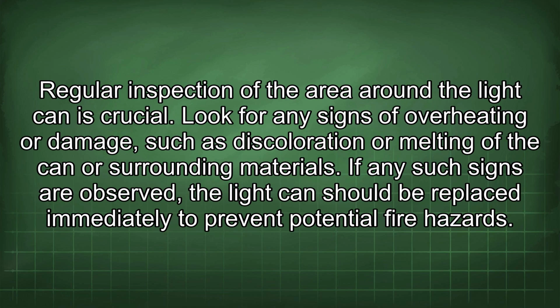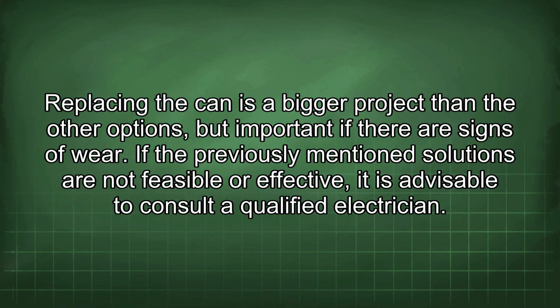Regular inspection of the area around the light can is crucial. Look for any signs of overheating or damage, such as discoloration or melting of the can or surrounding materials. If any such signs are observed, the light can should be replaced immediately to prevent potential fire hazards. Replacing the can is a bigger project than the other options, but important if there are signs of wear.